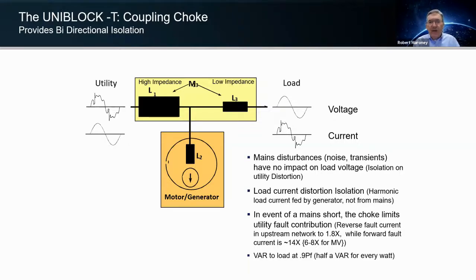Also, the choke provides us fault contribution of only about 1.8x upstream, but because of the low impedance component of it, it does allow up to 14 times fault contribution downstream to help clear faults when you have to clear those downstream breakers.